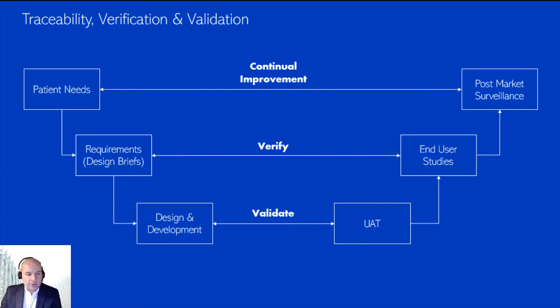You could look into IEC 62304. They've got a V there, which is a lot more complicated than this, and there's a bunch of them out there. But the point is that a key part of good software development, especially medical device software development, is that you need to validate and verify what you're doing, and then make sure you get that post-market surveillance feedback. And these are all formalized systems as part of your quality system.